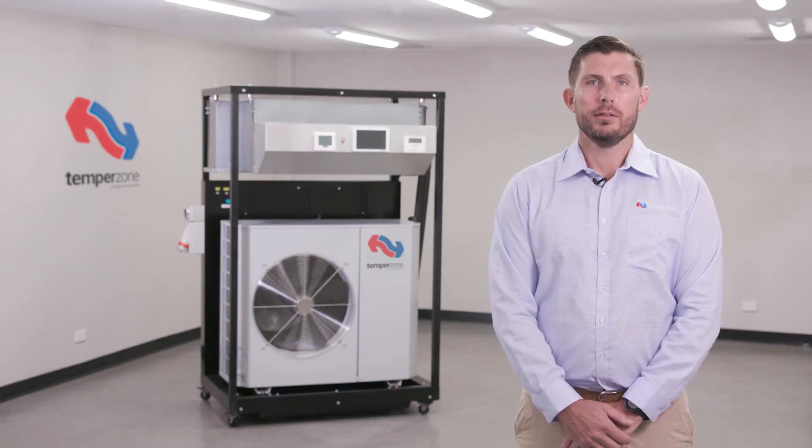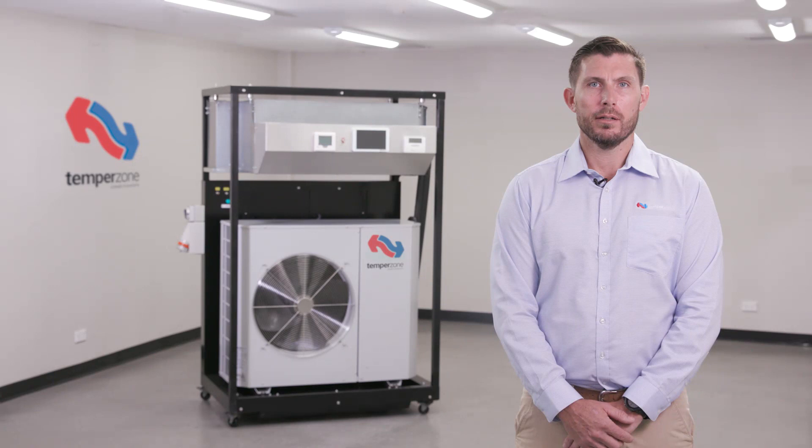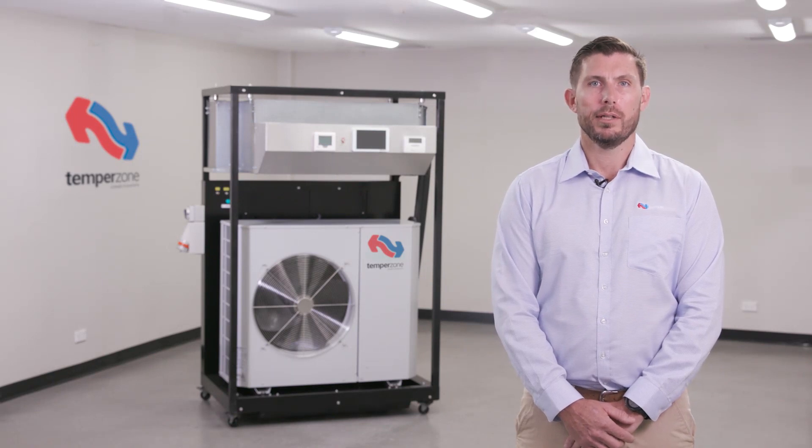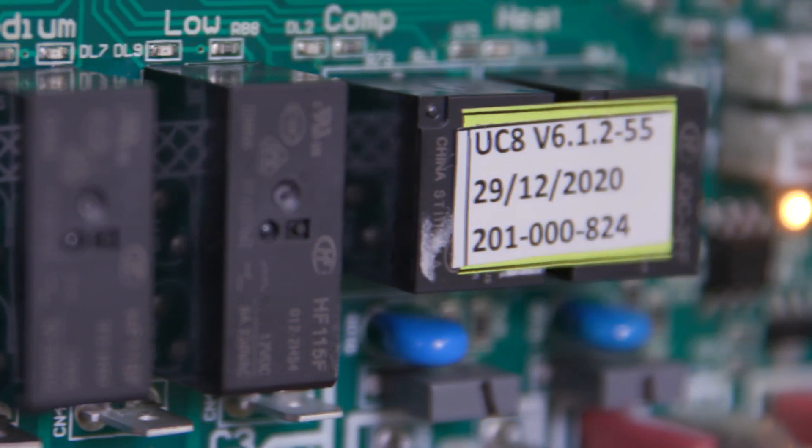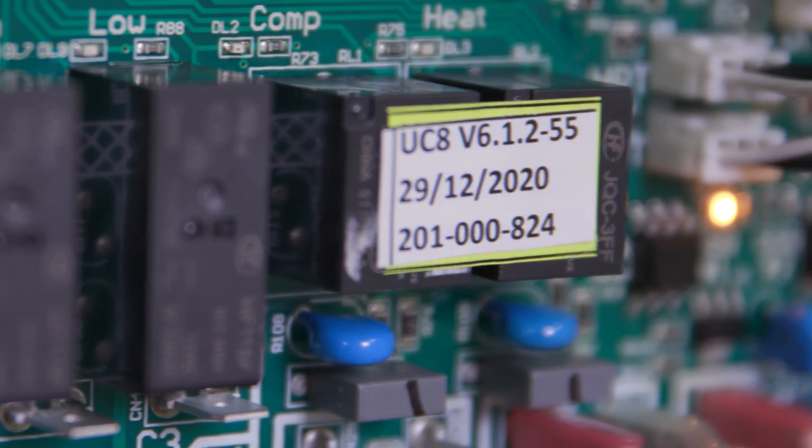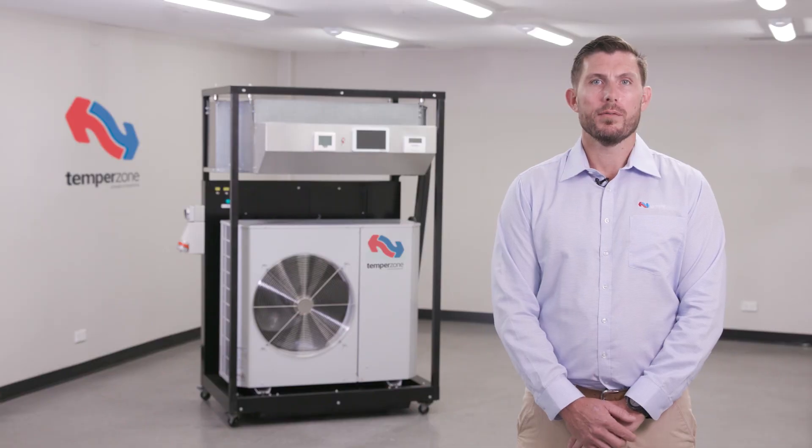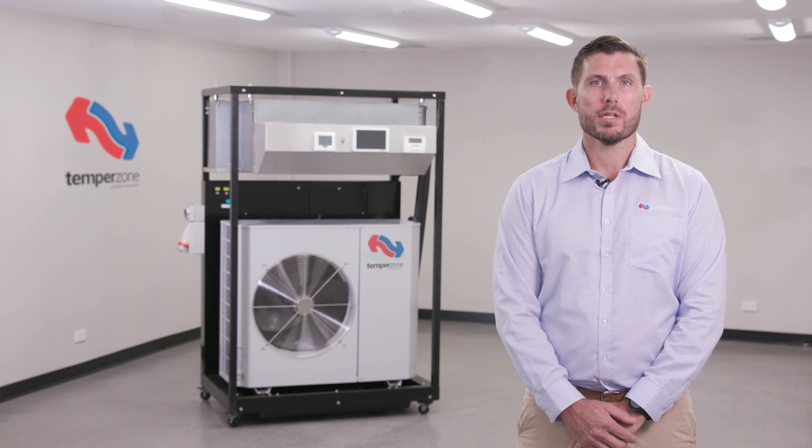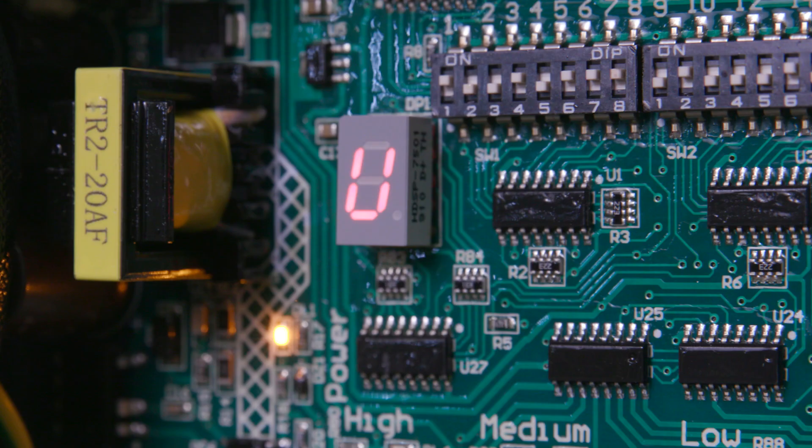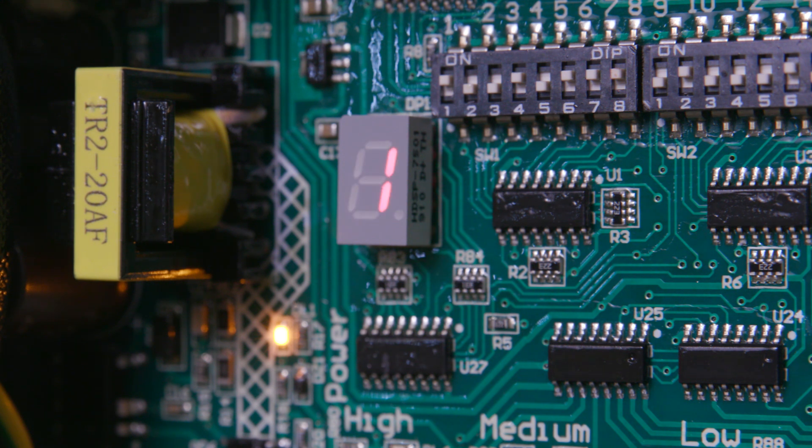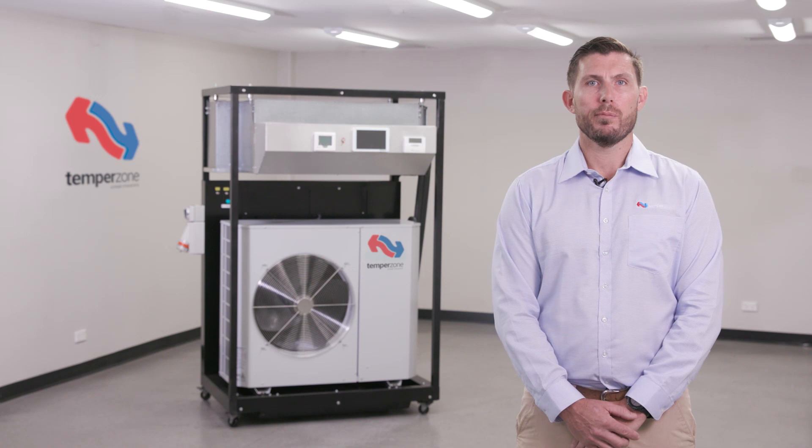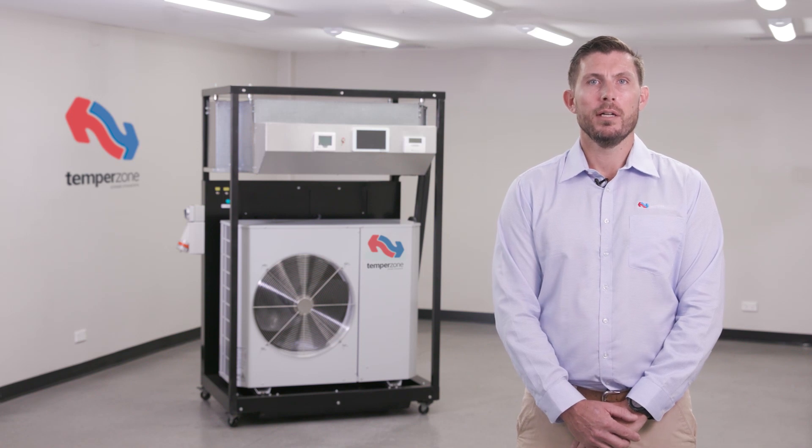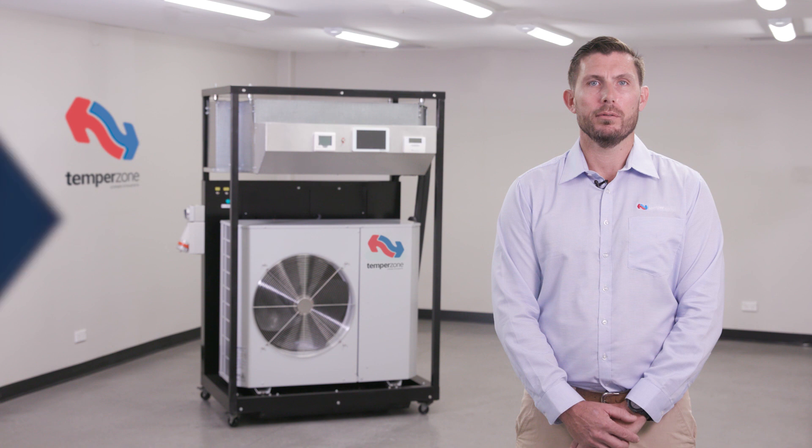Access to special modes using the SW3 push button is different depending on which version of the UC8 software you encounter. Software version can be seen on the sticker containing the UC8 part number. However, the more accurate way of checking software version is to reset the power and watch the UC8 initialization procedure. First displayed will be UC8 followed by the version number. Other helpful information such as the refrigerant type is also displayed on initialization. Further information regarding initialization can be referred to in the UC8 operation manual.